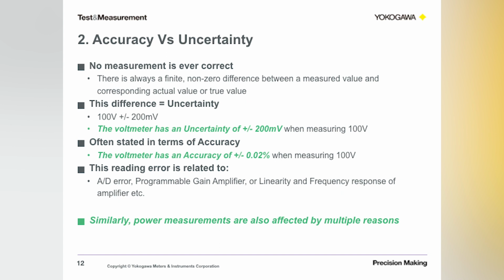Very commonly, instrument manufacturers will use the word accuracy to define this uncertainty. So in this case, the uncertainty of the above voltmeter can be stated as having an accuracy of plus or minus 0.02% when measuring a 100-volt signal at the 100-volt range. So the words uncertainty and accuracy are used interchangeably. One is referenced in an actual unit, and the other one is referenced in percentage.